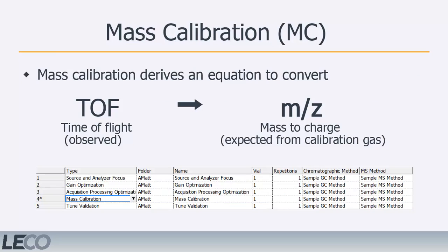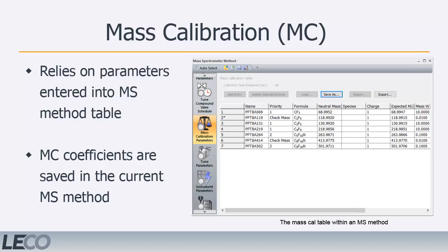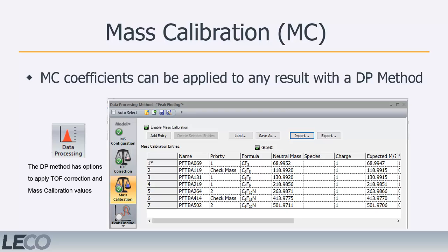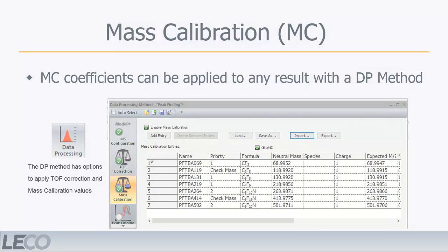The mass calibration derives an equation for converting between time of flight and mass to charge and saves coefficients to the MS method. The mass calibration is performed based on parameters entered into the mass calibration table within the MS method. The mass calibration coefficients can be applied to any previously collected data by using a data processing method as needed. Mass calibration involves complex processing procedures that are covered in detail in a mass calibration video.